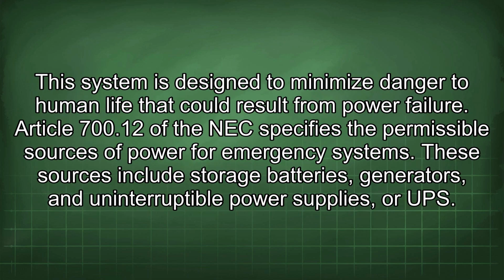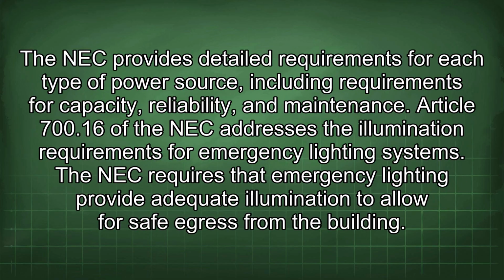This system is designed to minimize danger to human life that could result from power failure. Article 700.12 of the NEC specifies the permissible sources of power for emergency systems. These sources include storage batteries, generators, and uninterruptible power supplies, or UPS. The NEC provides detailed requirements for each type of power source, including requirements for capacity, reliability, and maintenance.